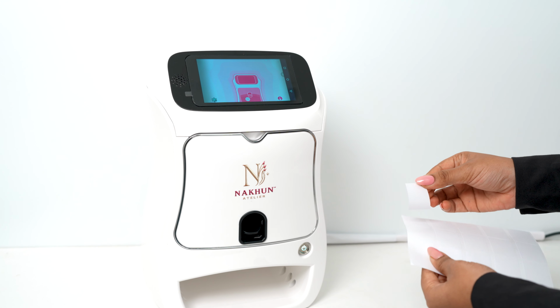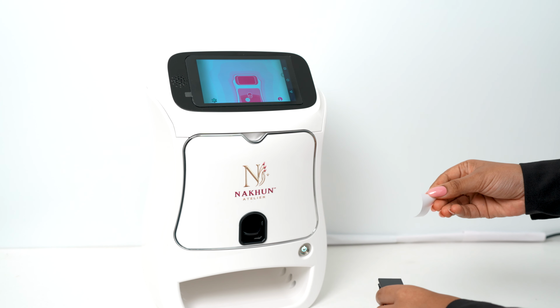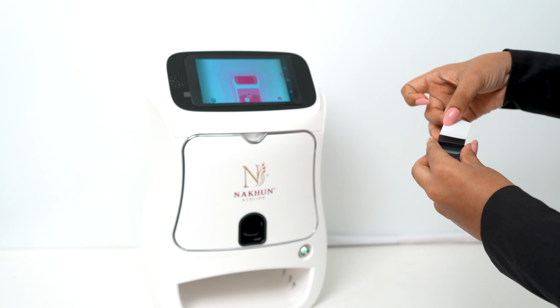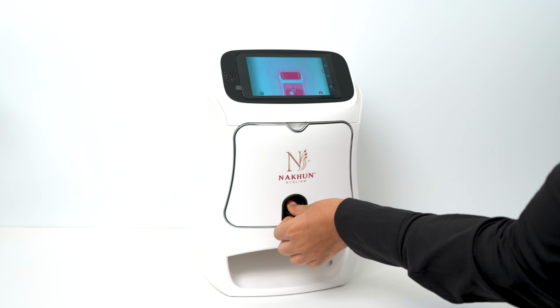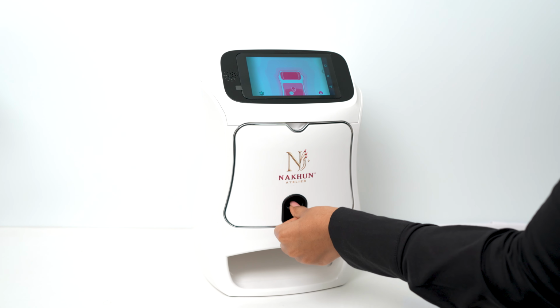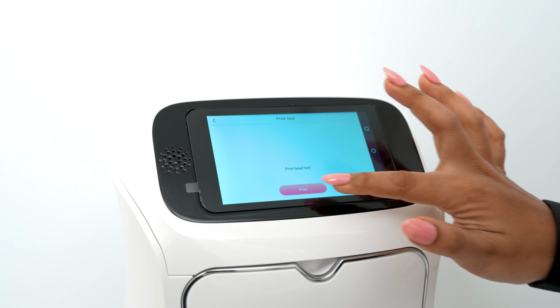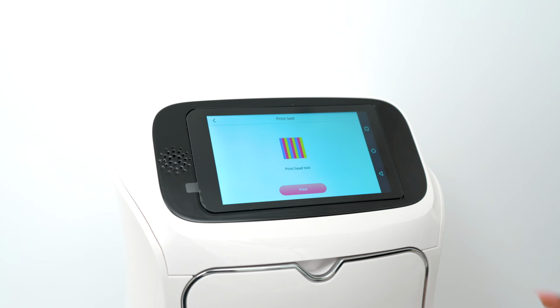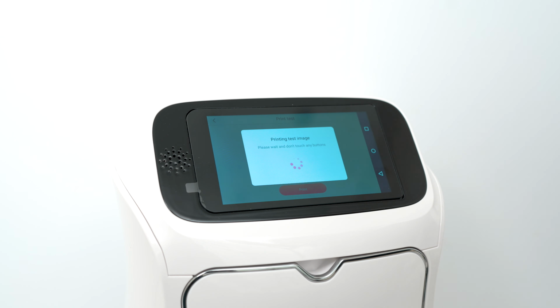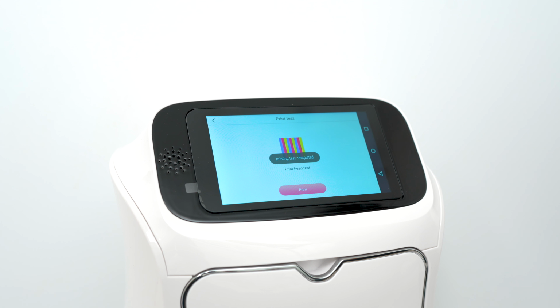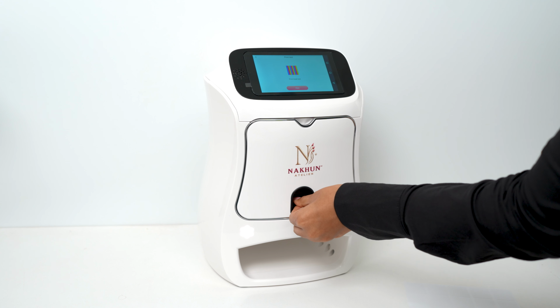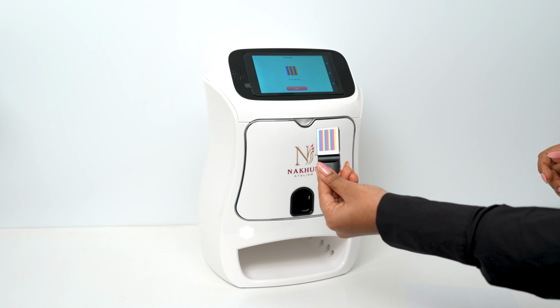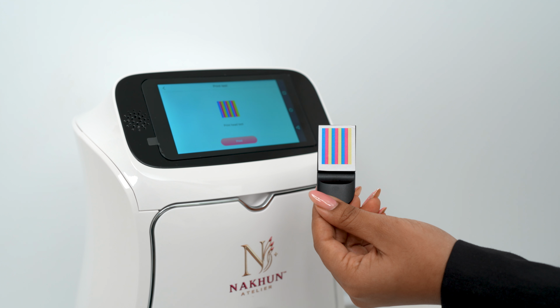Take the test paper and place it onto the print test base provided in the kit. Insert the print test base into the finger deck slot. On the screen, select Cartridge Test and tap Start. The machine will begin the printing test automatically. Once the test is complete, remove the finger deck and check whether the printed pattern is clear and properly aligned.